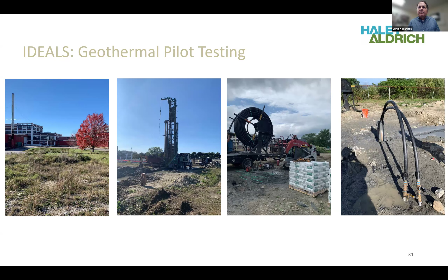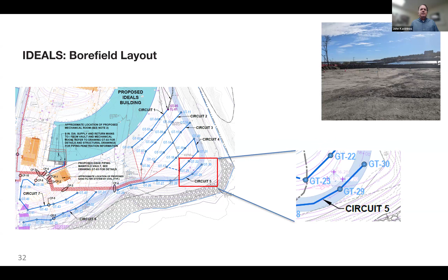So we will lay these out in, again, an open area. You see the slide on the right. That's the IDEALS site with the bay in the background, nice and level, prepped, ready for the drill rig. The boreholes are not piped individually into the mechanical room, but are grouped in circuits. We manifold the exchangers from the boreholes into a single pipe. That reduces the number of pipes entering the mechanical room. And again, all of the moving parts, all of the equipment driving fluids through the bore field are in the mechanical room. So no pumps to service out in the bore field. And I think that's the end of our presentation.